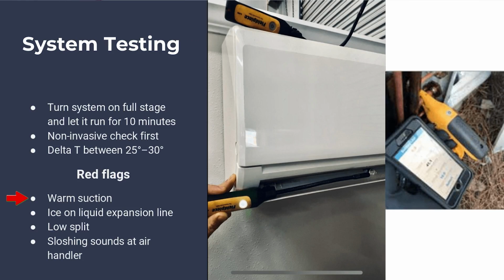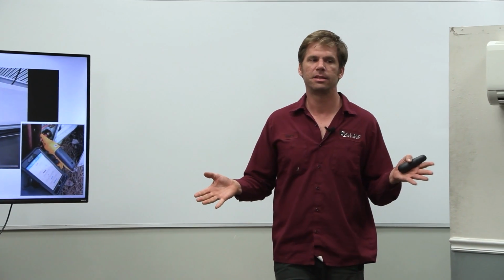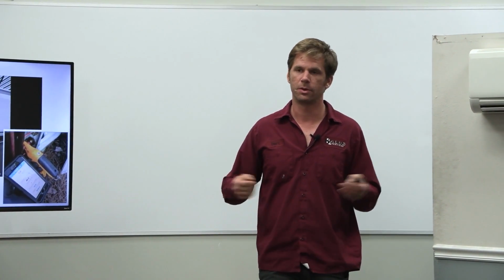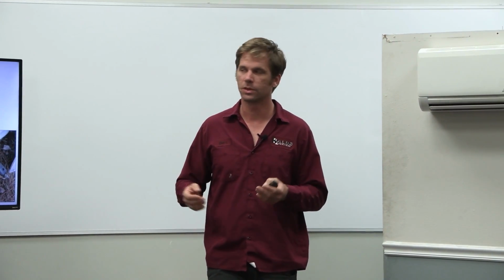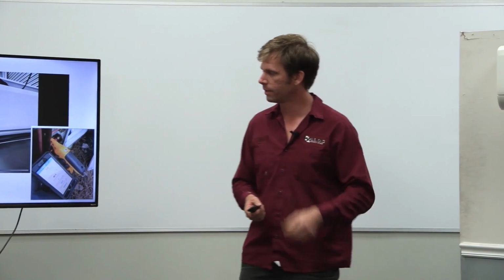We have a warm suction line. We have a low split. We see ice forming on the expansion line. Now, I have seen a system that's been sitting off for a really long time, you first turn it on, a little ice is there, and within a couple minutes of run time it's gone. So, as with everything else, you turn your system on, give it 10 minutes to run before you check.